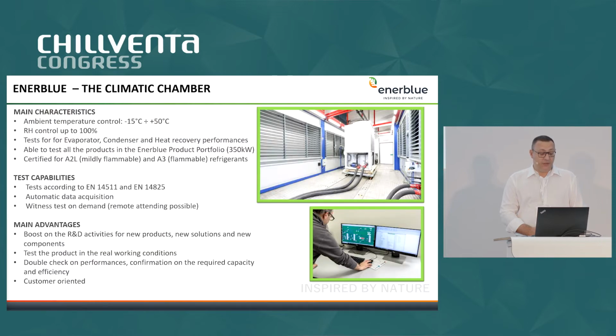One of our strength points is the climatic chamber. We are able to test all the units we produce, all the units in our catalog, in our climatic chamber, testing all the points around the working limits. And in this way, we are able to satisfy all the customer needs in terms of reliability and performance confirmation.